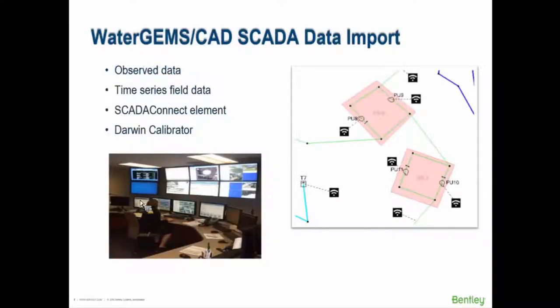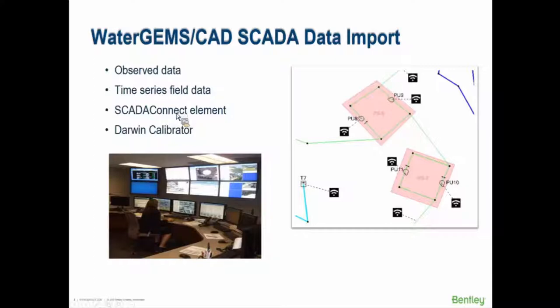Let's look at the first use case: bringing SCADA data into the model. We have several ways of doing this in WaterGems. We have observed data, where if you're in a graph you can point to observed data in a spreadsheet and bring it in. Time series field data is another way. These are older technologies. The big one to focus on today is the SCADA Connect element — those little black things that look like radio signals — where you place a model element that represents a SCADA signal. Darwin Calibrator also has ways to import SCADA data, but I'll focus on the SCADA Connect elements.